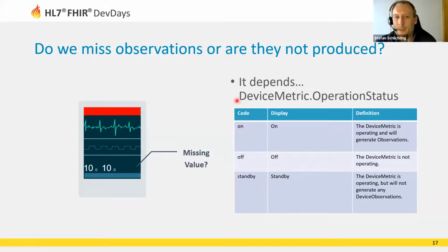If we now look at the device metric, we would see that the device has the capability of, for example, measuring the pulse, but we would look into the operation status and see, okay, maybe it's off for whatever reason, or it's in standby, or it is actually measuring. If we then don't see any value here, this might be an indication that there's a problem and that we maybe missed some observation measurements.